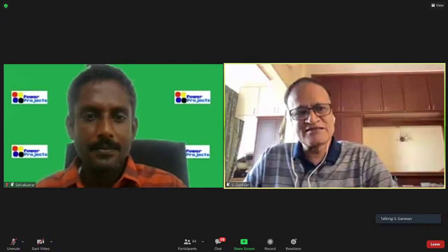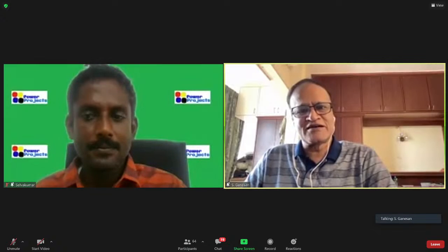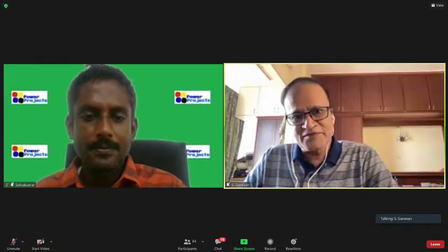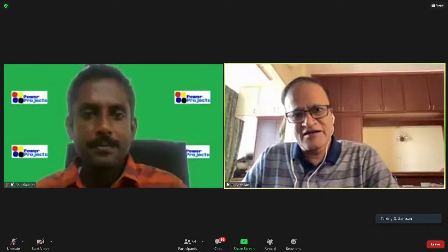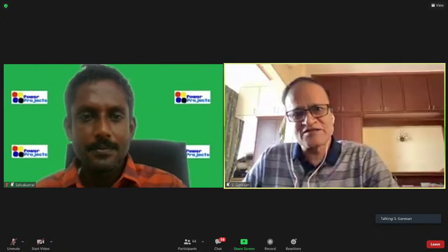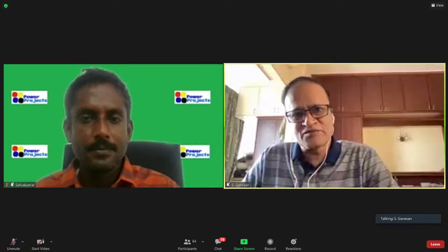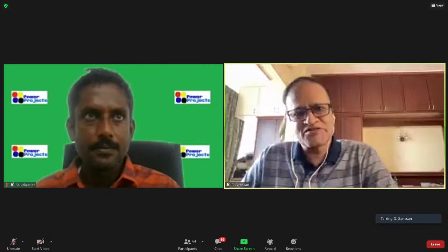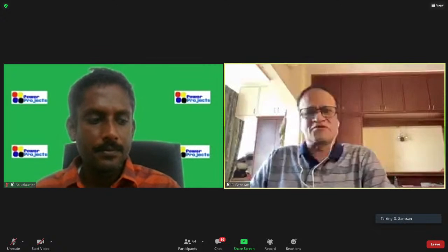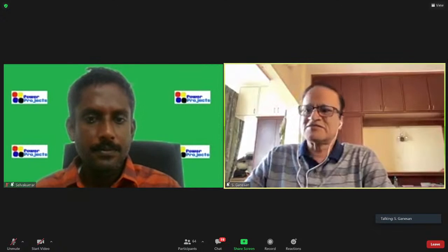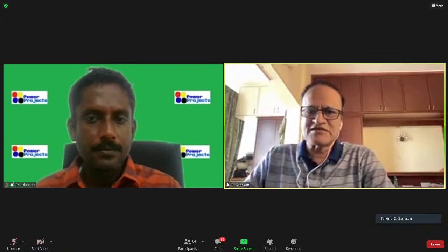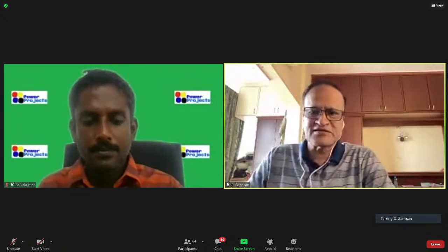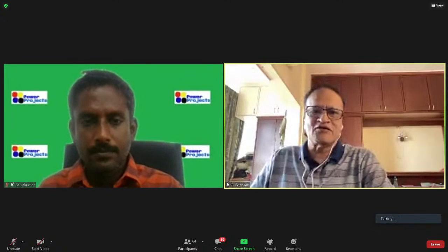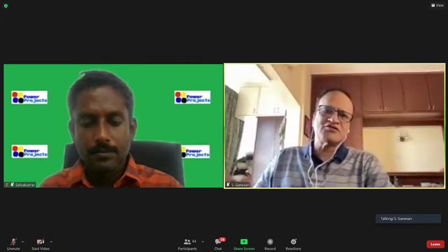So the idea is that you should drive the communication guys, not the other way around. That's what I'm trying to get at, because ultimately we are protecting the system - that is the number one thing we need to do for anything in a power system. Don't let them drive you around. You say, I want this signal within 3, 5, or 10 milliseconds, this is the reliability I want - you are the monitoring, control, and protection engineer.